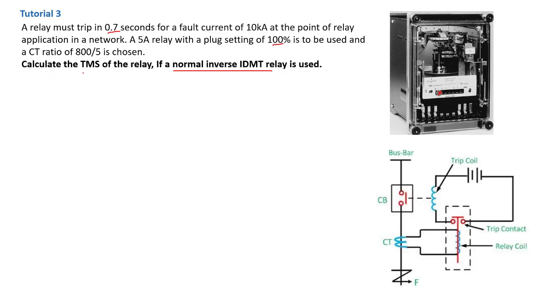In this tutorial we need to calculate for the normal inverse characteristics. If you've watched my tutorial on IDMT relay characteristics curves, I described in some depth what these characteristics mean and the formulas involved. Moving forward, we need to find the TMS — the Time Multiplier Settings — which relates to the disc and the setting current together, determining how that relay is going to rotate.